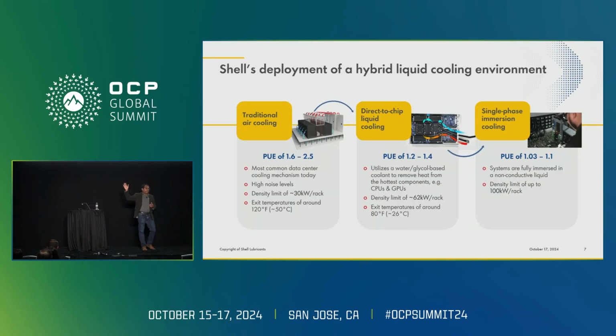So this is our journey, for Skybox, this one data center. In 2019, we started with air cooling, and we still have a portion of the building with air cooling. Our PUEs are around maybe 1.6 to 2.5. 2.5 is a high side because one of the data centers we have in Asia Pacific is really bad with respect to energy efficiency. But because we represent HPC for Shell, we know the ranges we deal with when going for air cooling.